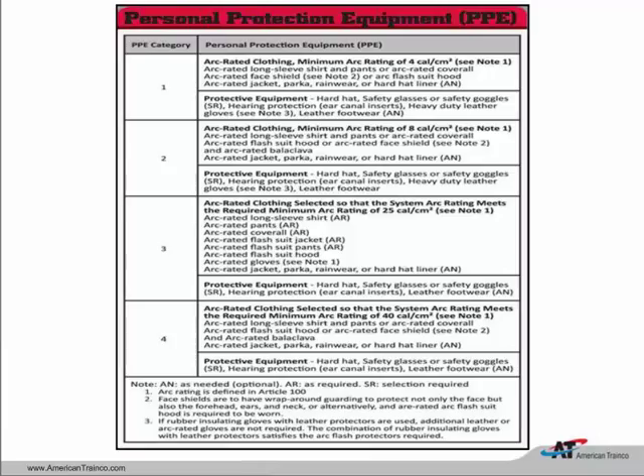Those would be Z87 eye protection for us. We do have to wear the ear canal inserts, so we can't wear the muffs. Can't have the muffs on our head. We have to wear those. And notice that it does say heavy-duty leather gloves in 1 and 2. When we get to PPE Category 3, no longer are we going to see heavy-duty leather gloves. We are going to see arc-rated gloves. So this is talking about our leather protectors that go over the rubber insulation. Those leather protectors will have to have an arc rating on them when we are above 8 calories of energy.